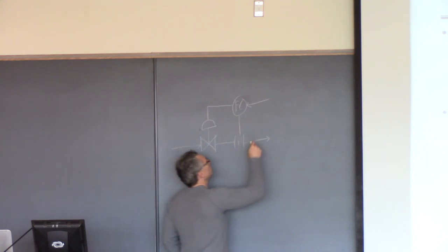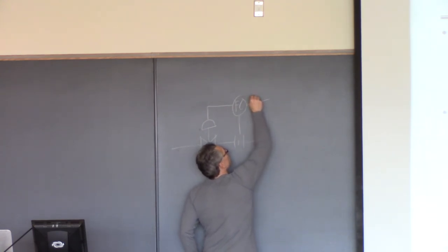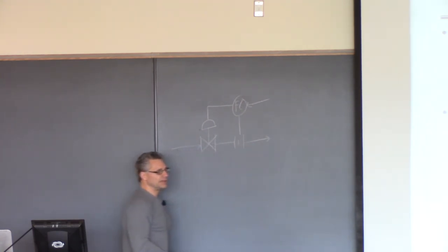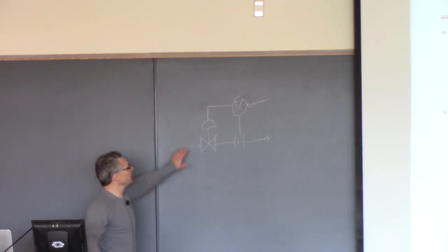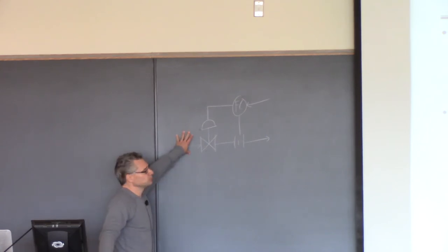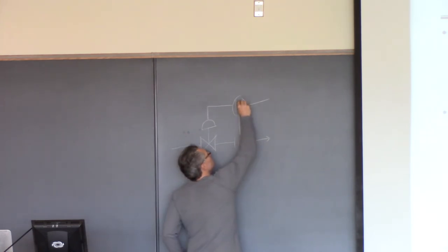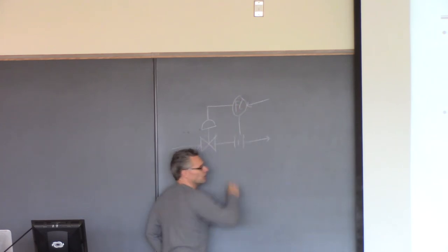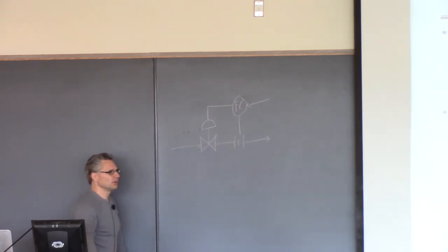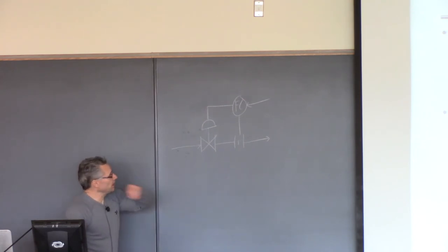The temperature controller determines what this flow set point should be. So anytime you're controlling a flow, there will be a flow controller, okay? And if you want to use this flow to control temperature or pressure or whatever, the controller that you design is going to send a set point to a flow controller, almost always. So my argument is when you use flow to control something, which is almost always, it'll almost always be cascaded to a flow controller for the reasons I just explained up there.